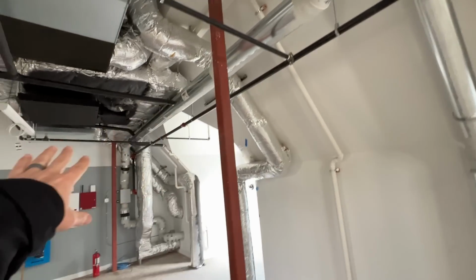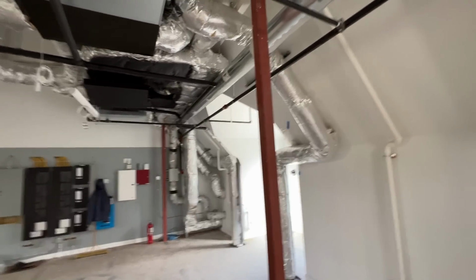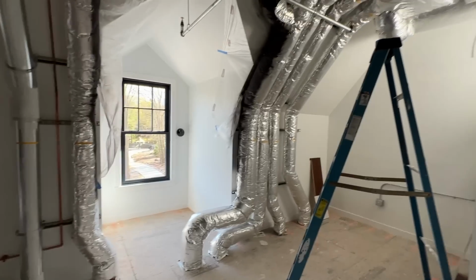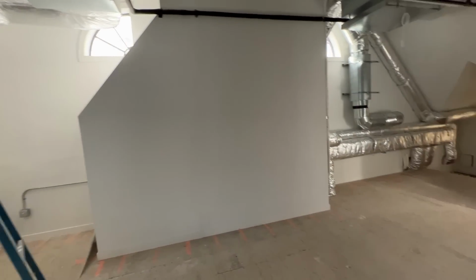You'll also notice all the ductwork in here is rigid duct, no flex, and I'm a huge fan of rigid ductwork. The rule I've followed over the years is to run all our trunk lines and supply lines in rigid. If you need to transition to flex for the last 10 feet, that can quiet down the airstream and be a good compromise. If you need to run flexible duct for cost reasons, do it on the return side, where you're not as worried about future cleaning. On the supply side you really want to be able to clean those ducts and have good air sealing, so rigid is the way to go.